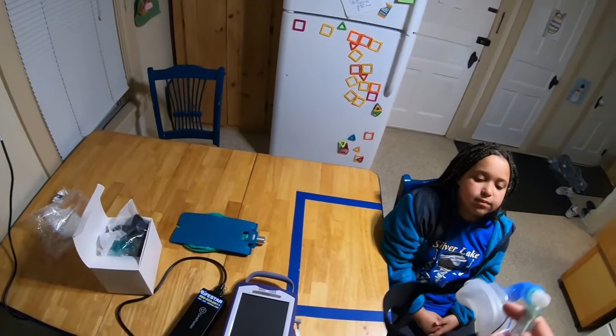All right, the other method of doing this is everything is all hooked up already. We have our elbow, we have our end-tidal CO2, we have our filter, everything is there, and we turn on the vent. We would have already tested it for today, first thing that we do at the start of a shift. And so select non-invasive. It's going to scream, and we're going to set up everything here. And I'm going to do 8/4, so you can see the 4/4. It's screaming, it's unhappy. You can hear it go, and it's trying to find somebody breathing. It's obviously not finding anybody breathing, and eventually it will stop. And so it'll say patient circuit failure because it didn't find anybody to breathe with.